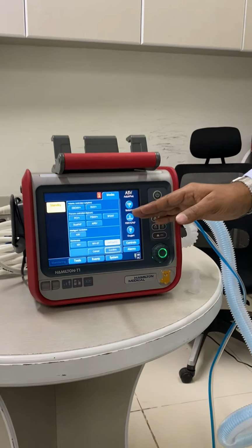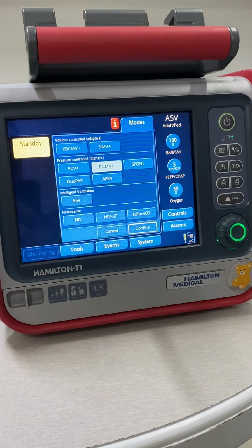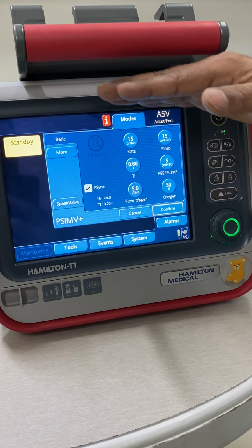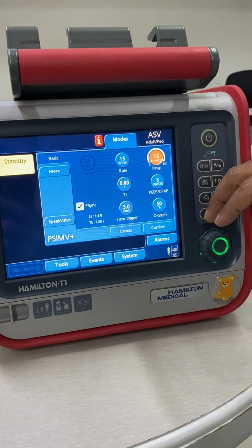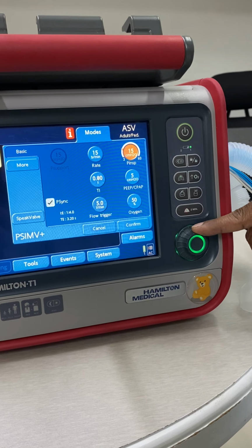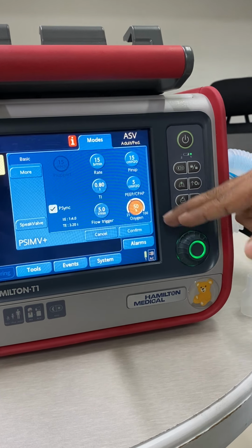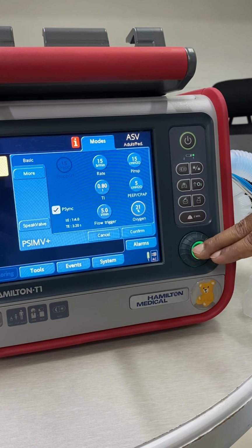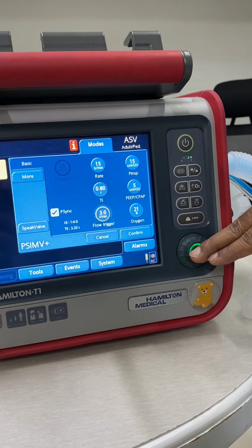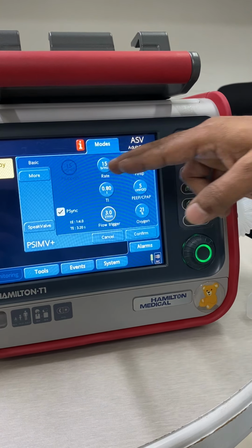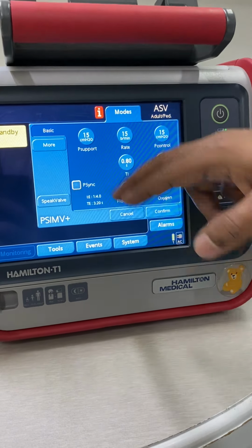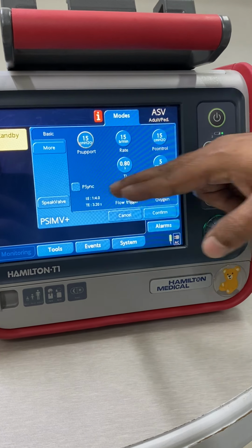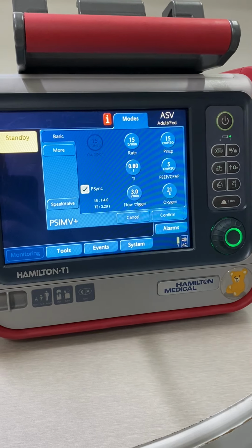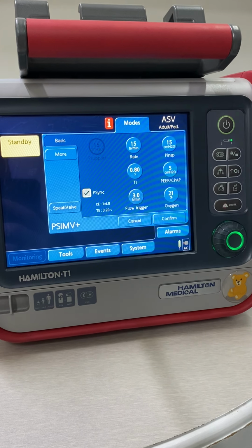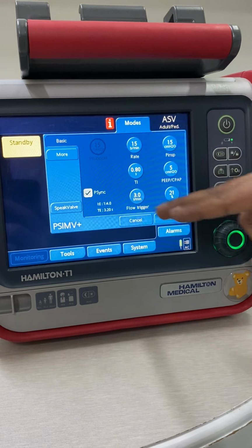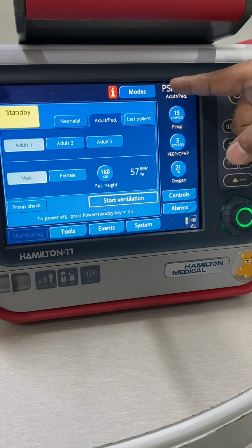Okay. So suppose if you want to choose any mode, choose the mode like PSIMV, pressurized IMV, confirm it from here, then the settings of that mode will come up. You can choose the inspiratory pressure, choose whatever you wanted, confirm it. For O2, I'm not connected to the oxygen source, so I'll make it 21. And the flow trigger, the lesser the number, the more sensitivity, I time, and the rate. And if you want a pressure support separately, you can avoid the PSync and you can set up a separate pressure support. If you sync the pressure support, it will come like an inspiratory pressure acting as a pressure support upon the flow cycled breath or the patient initiated breath. So once you choose the parameters, you can confirm it, it will be in that mode, PSIMV.